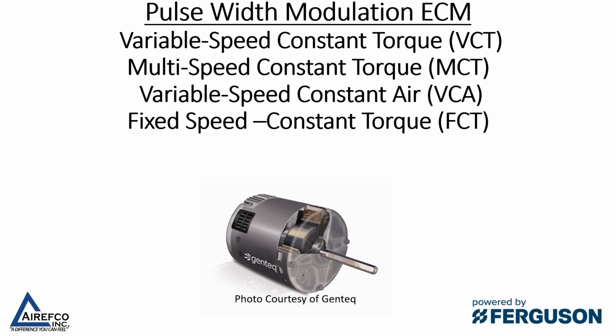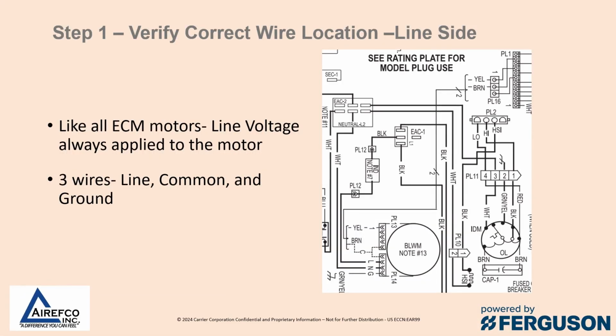This video is going to cover troubleshooting the new ECM motors that you will find on the NFC furnaces and air handlers put out by Carrier and Bryant. The first thing to recognize about ECM motors is that all ECM motors have line voltage always applied to the motor. There'll be usually 3 wires, the line, the common, and the ground, that supply 115 volts or 208/230 to the motor.